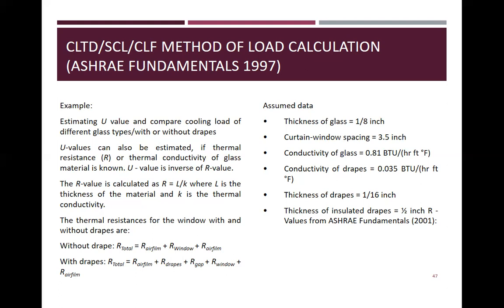So assume data: thickness of glass is 1/8 inch. Curtain window spacing is 3.5 inch. Conductivity of glass is 0.81 BTU per hour square foot. Conductivity of drape is 0.035. Andun yung sa mga tables there. Thickness of drape is 1/16 inch. Thickness of insulated drape is 1/2 inch. Values from ASHRAE Fundamentals 2001 or 1997.